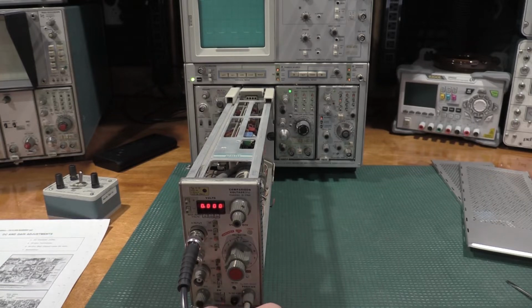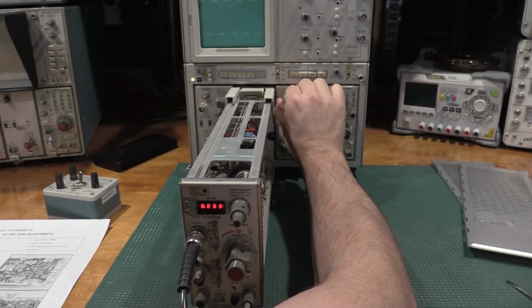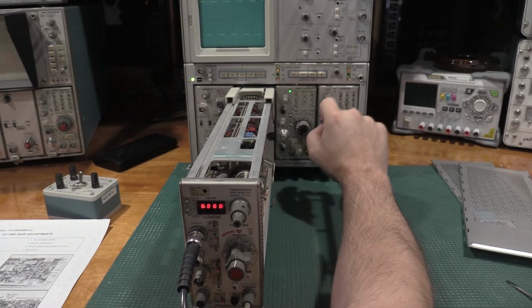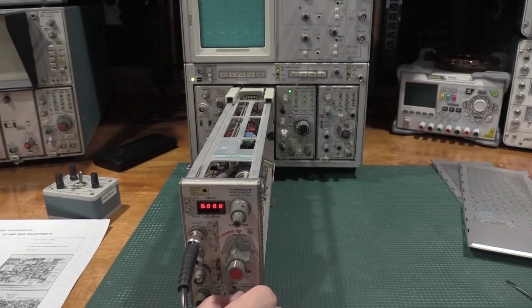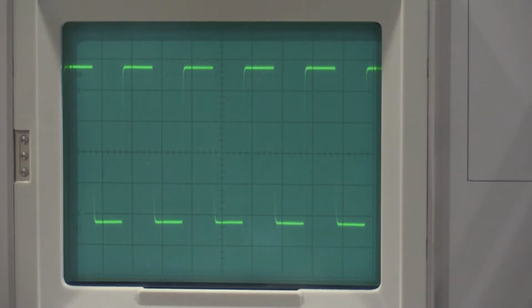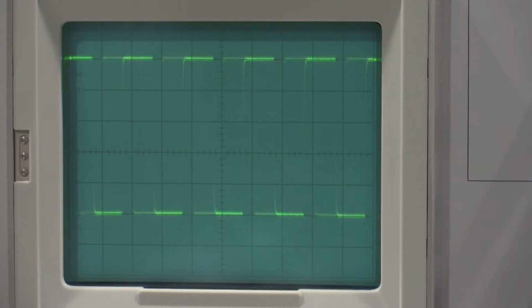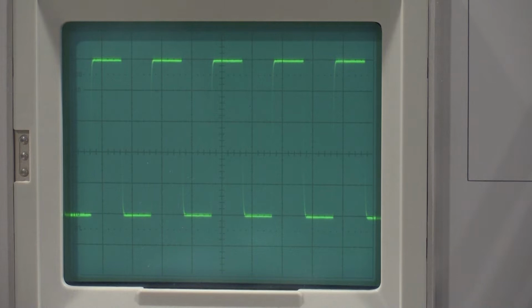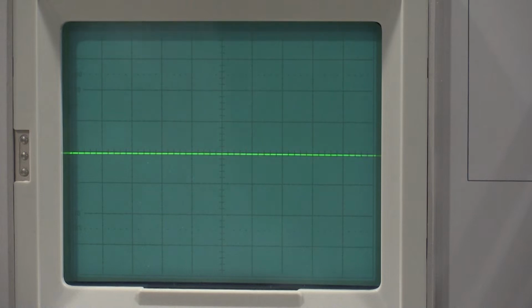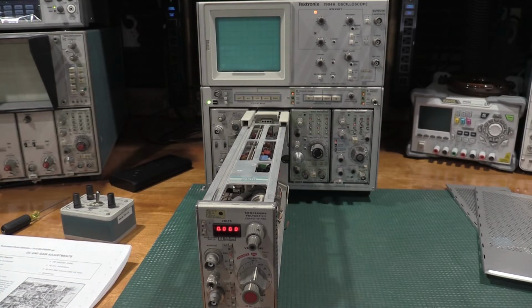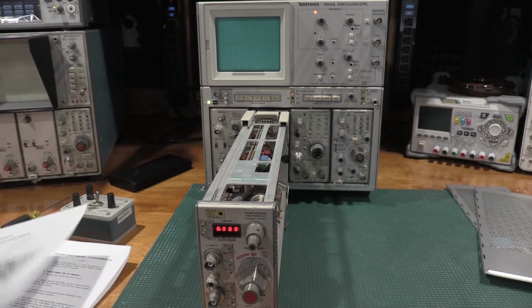And we'll position this. And let's clean up some triggering here. High frequency reject. Okay, and our calibrator signal. Our gain is good. It's moving around a bit because of the thermals, but we have a 5 millivolt peak-to-peak signal, and we have 5 millivolts per division. So our gain is in good shape. So sensitive, that's going to come back, and that's probably going to be a fixture of this alignment procedure, just the sensitivity.